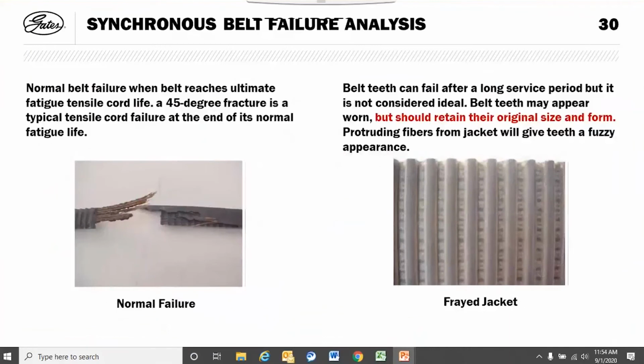So Jerome, just out of curiosity, is there a typical failure reason that you see in the world of belts? The vast majority, it's like 57% of the time we see failures from belts is lack of tension. And again, that's because somebody's using their calibrated thumb. We have belts sent to us every day. The engineers take a look at them and they can just pick it up and go, lack of tension, lack of tension. The vast majority of the time, it's from the lack of tension.